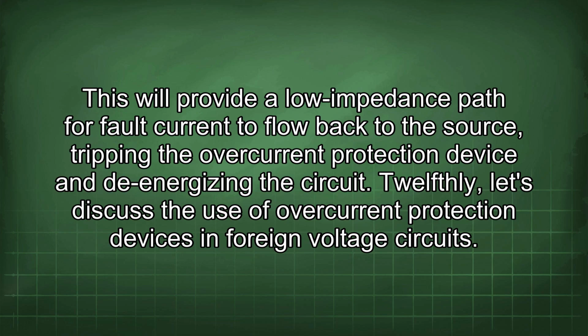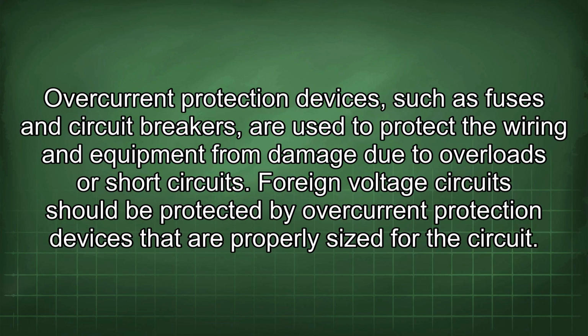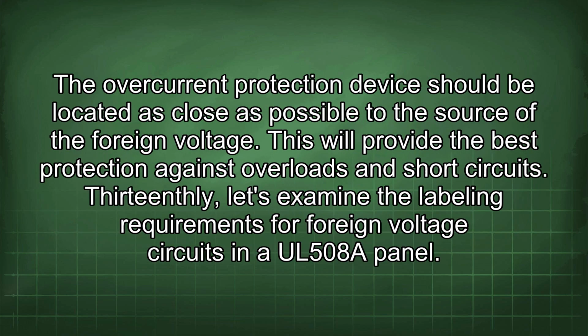12thly, let's discuss the use of overcurrent protection devices in foreign voltage circuits. Overcurrent protection devices, such as fuses and circuit breakers, are used to protect the wiring and equipment from damage due to overloads or short circuits. Foreign voltage circuits should be protected by overcurrent protection devices that are properly sized for the circuit. The overcurrent protection device should be located as close as possible to the source of the foreign voltage. This will provide the best protection against overloads and short circuits.